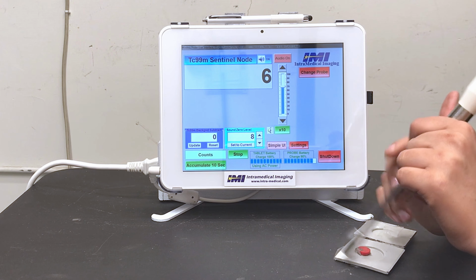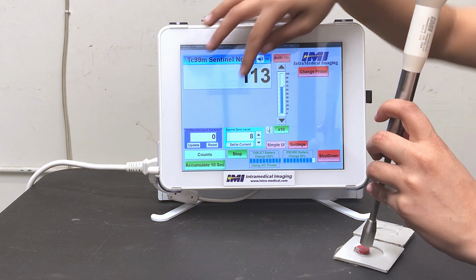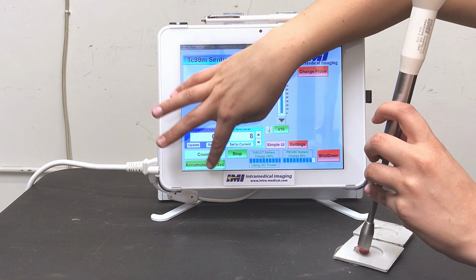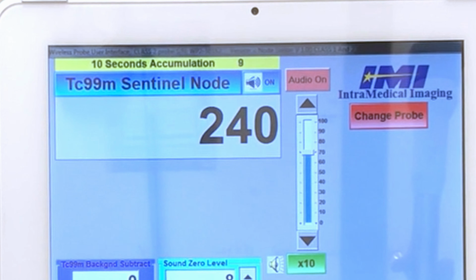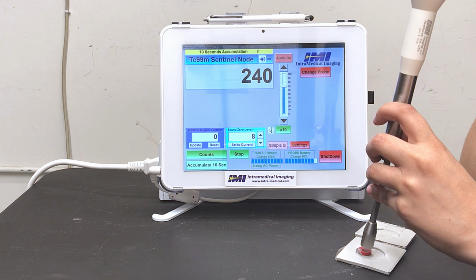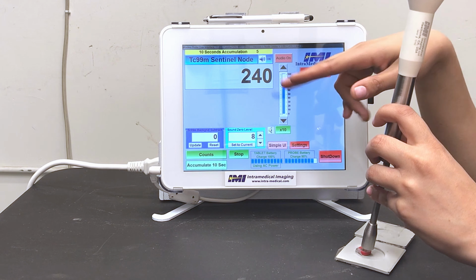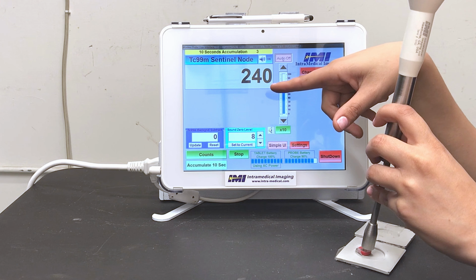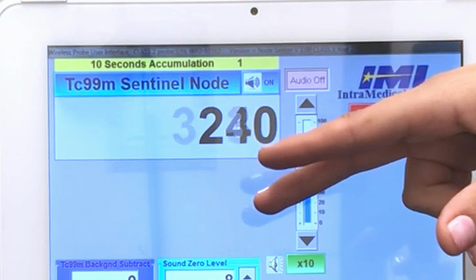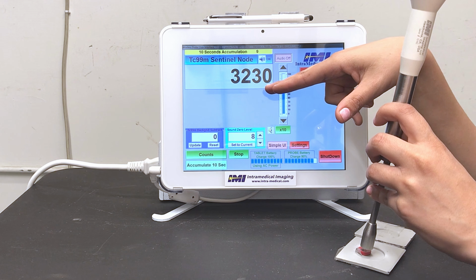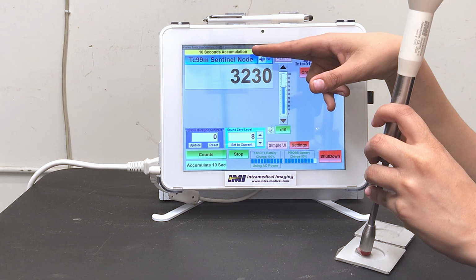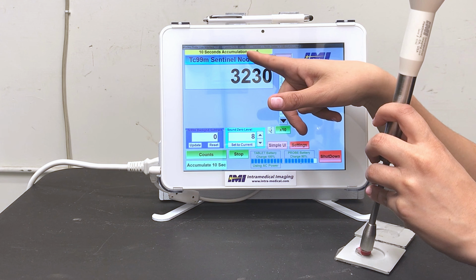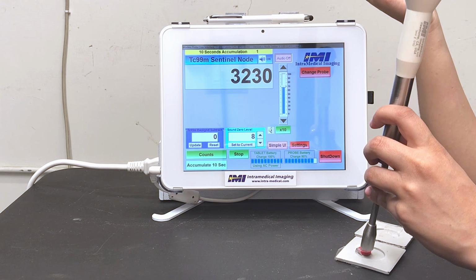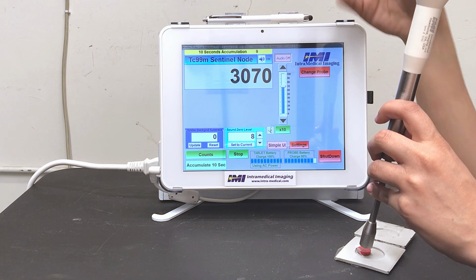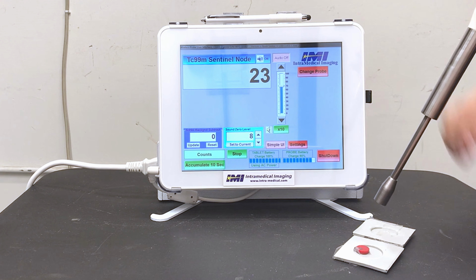Accumulate 10 seconds is a summation of the counts in a certain area over 10 seconds. After selecting the green button named Accumulate 10 seconds on the bottom left of the screen, a yellow timer will appear above the TC99 count display. After each round of 10 seconds, the summation or accumulated counts for those 10 seconds will appear for around 3 seconds to be recorded. This will continue until selecting the green Counts button, which will allow you to return to the normal counts.